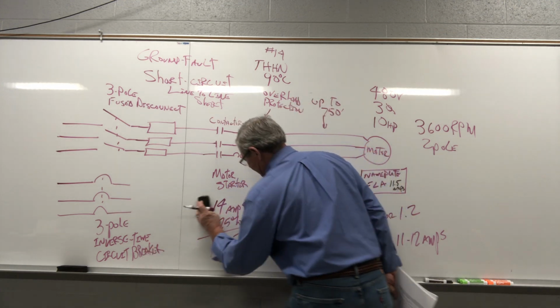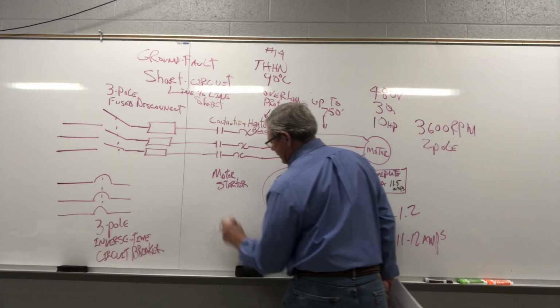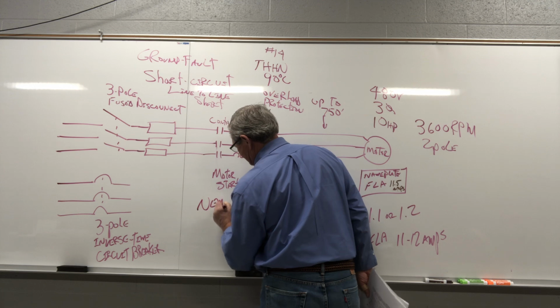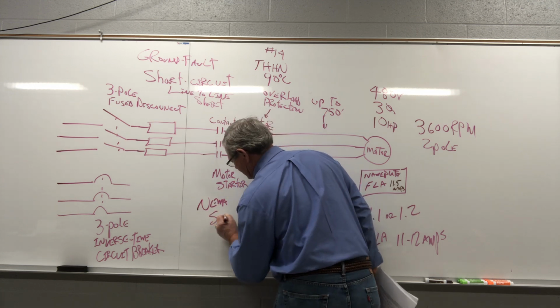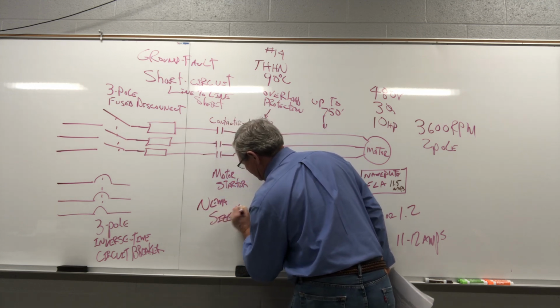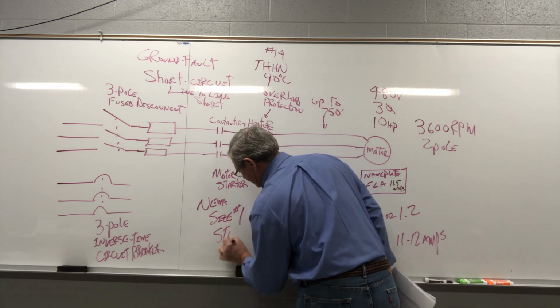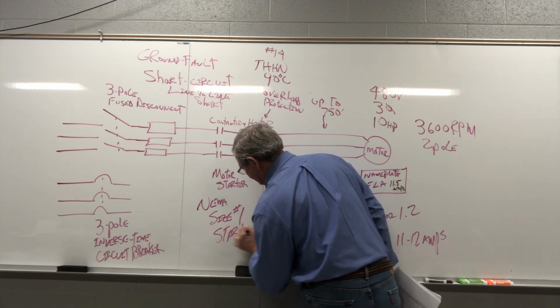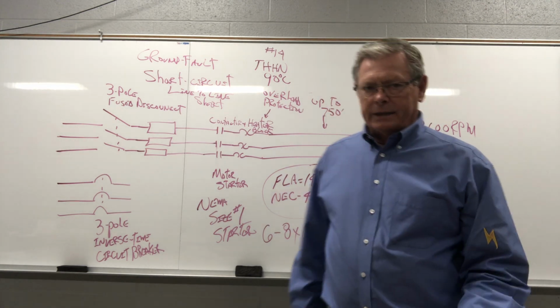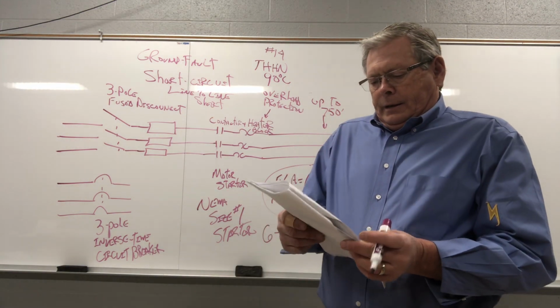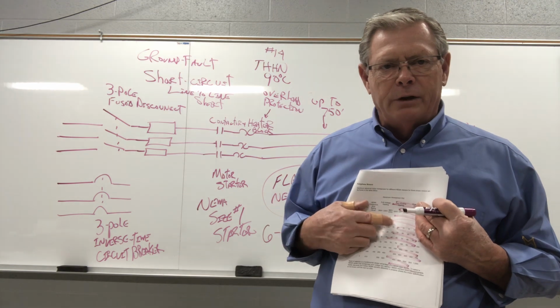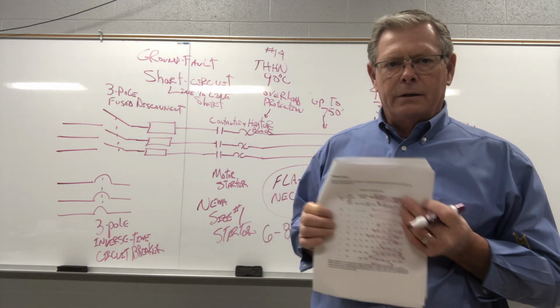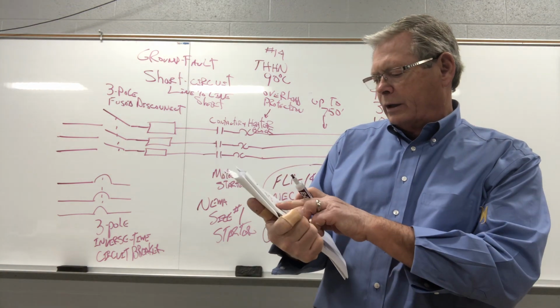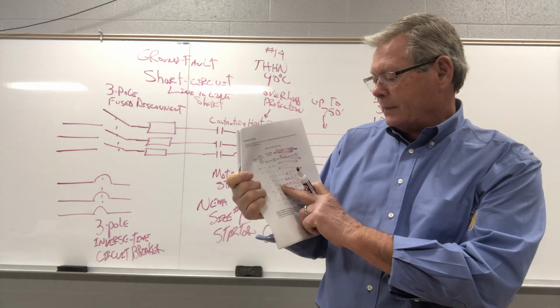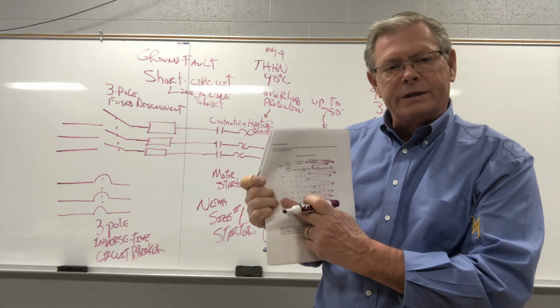So, now we know what size starter. Now, if we were to cut the application voltage down to 230, that same 10 horse motor, if we look at under the 230 column, and we go down, we see that would take a size 2. And here's the reason.